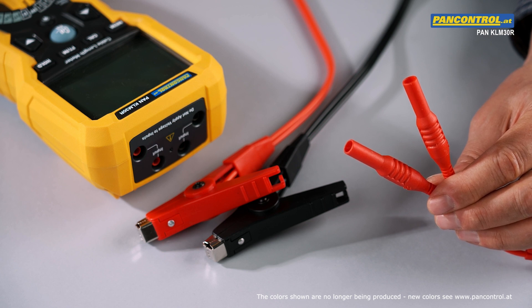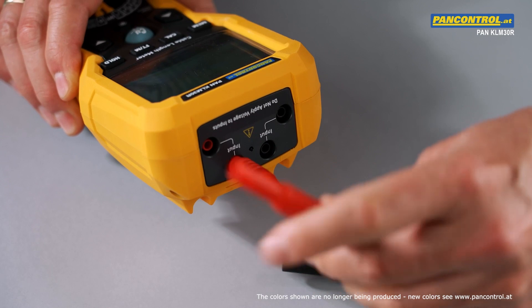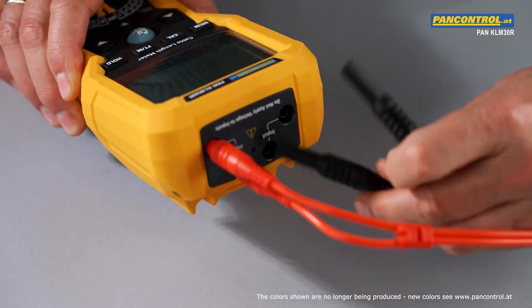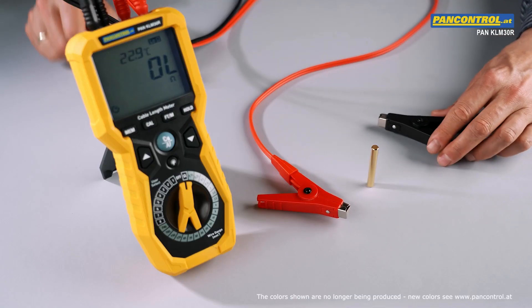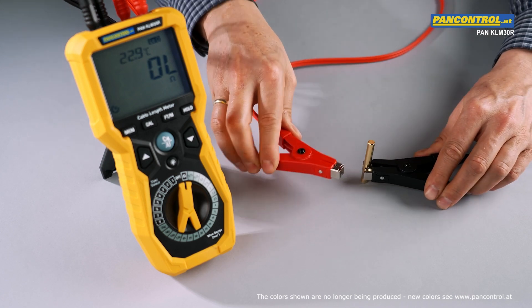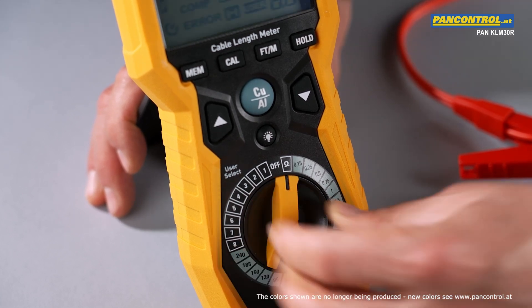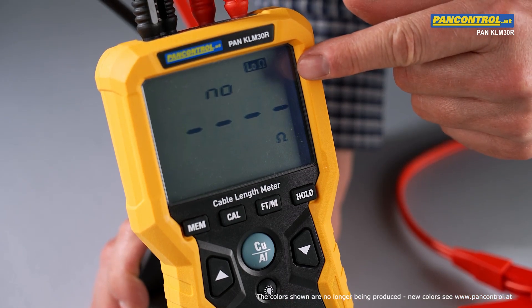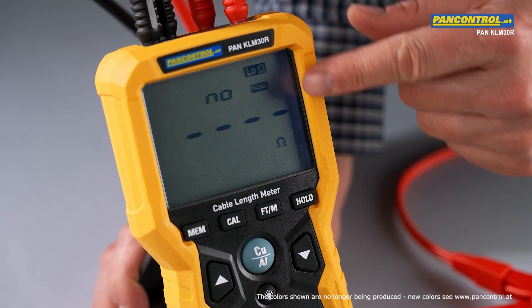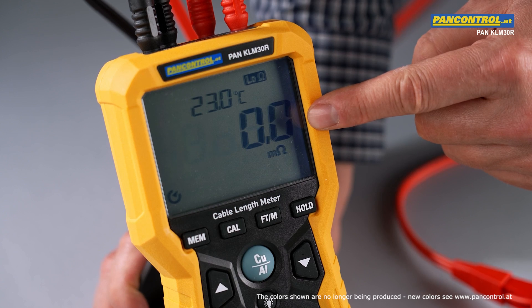The meter first measures the inner resistance of the test leads and deducts this value from the total measuring result. Now the test leads are connected to the meter. For calibration, both alligator clips are connected to the calibration bar. With the rotary switch set to resistance measurement, we press the cal button. After the display shows two times yes and no, we press the memory button and the message done shows the meter is ready for measurement.